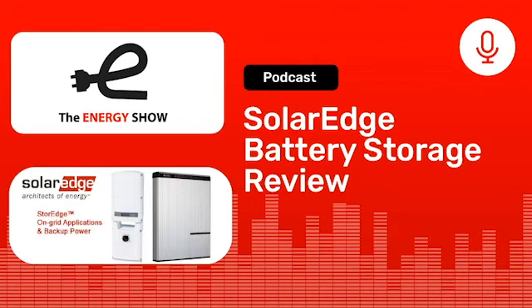If you have, in this example, a 4,000 watt system with this 10 kilowatt hour battery, about 70% of the solar energy the PV system generates is storable in the battery every day. So you'll be able to store 10 kilowatt hours of power. If you drain the battery down close to 0 every day, the system will be able to fully replenish it, though usually you don't drain the battery completely.